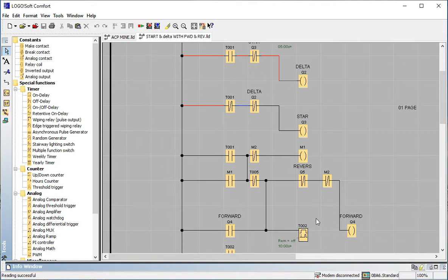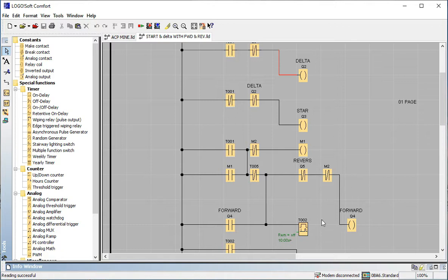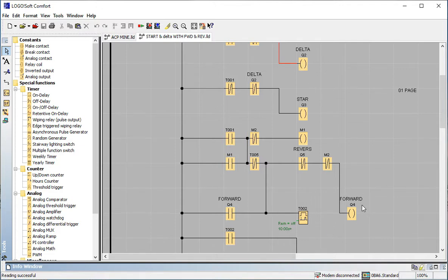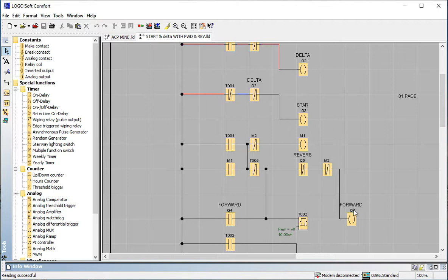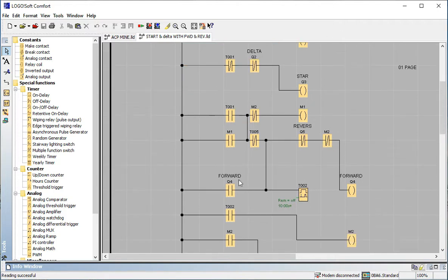T01 NO opens to M1 — M1 is latching here. This is connected directly to Q4, so when delta is connected, forward (Q4) is also running. Delta and forward are connected to each other: when delta is connected, the motor runs in the forward direction. If you want a delay time, a timer is available, but a delay is not needed here since delta connects and direction is maintained. T01 NO becomes NC, memory M1 goes NO, and Q2 (delta) and Q4 (forward) are both on simultaneously.